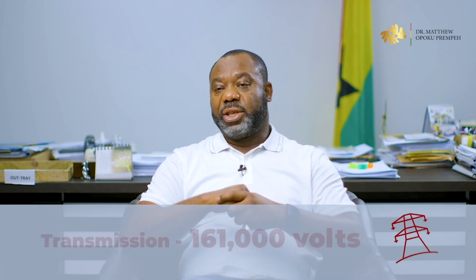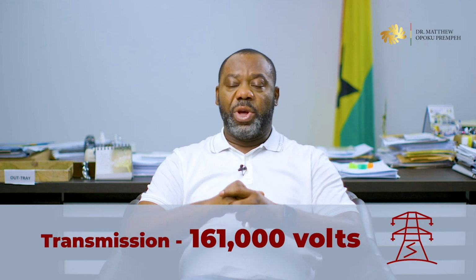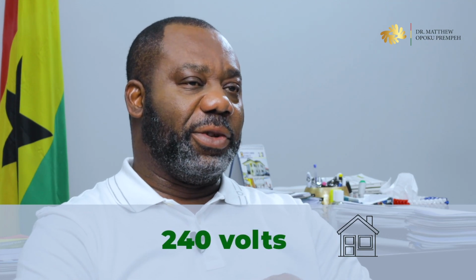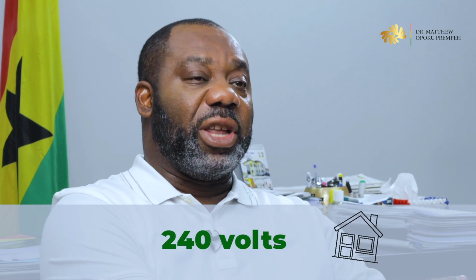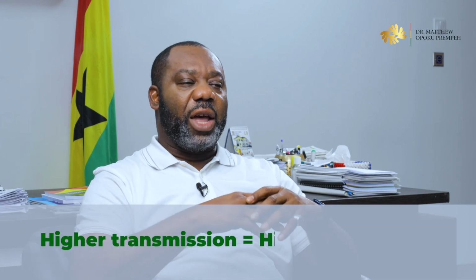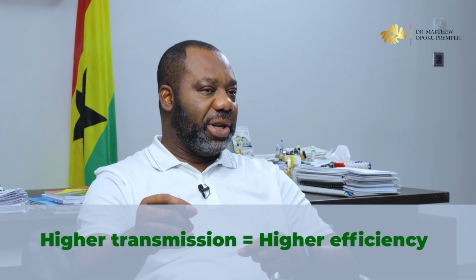To send enough power to a region, you need to transmit at high voltages, normally 161,000 volts in Ghana. Compare that to the normal electricity in our homes, which is 240 volts. Transmitting from the generator to the distributor goes through wires that concentrate it up to 161,000 volts. Some networks do have 330,000, which we are trying to modify in our transmission network. Some even go to 400,000 and 500,000 volts. The higher you can transmit, the more efficient the transmission is.